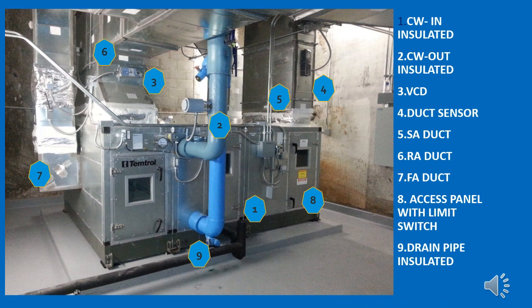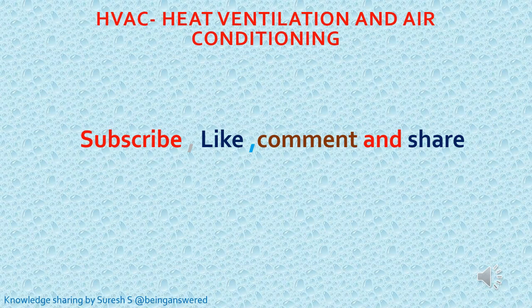You can see the side view of the AHU with chilled water pipe in and out, and ducting for fresh air, exhaust, supply air, and return air connected. Chilled water in and chilled water out are insulated pipes. A volume control damper is used to maintain the volume of air going to the conditioned area. A duct sensor is used on the supply air duct and return air duct, and there is a fresh air duct. An access panel with a limit switch will be present, and the drain pipe is insulated.